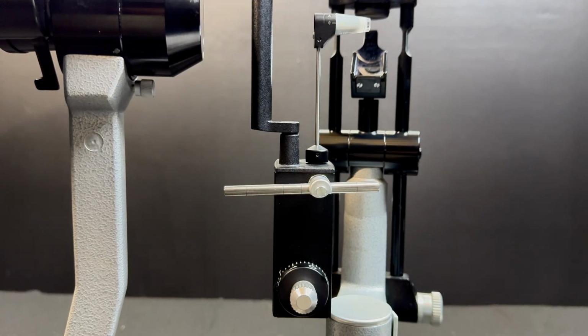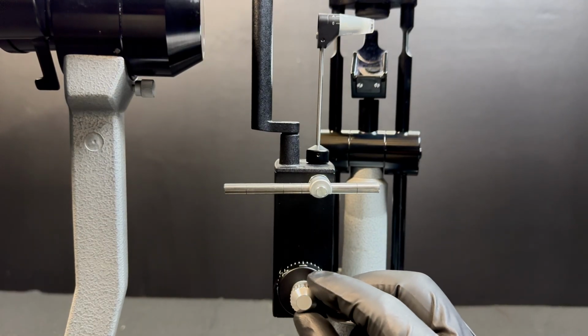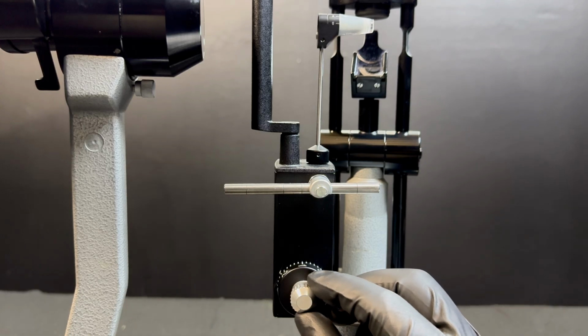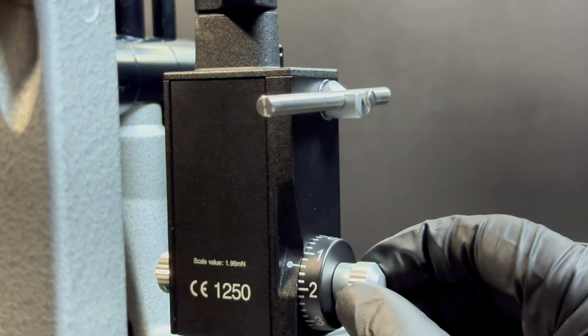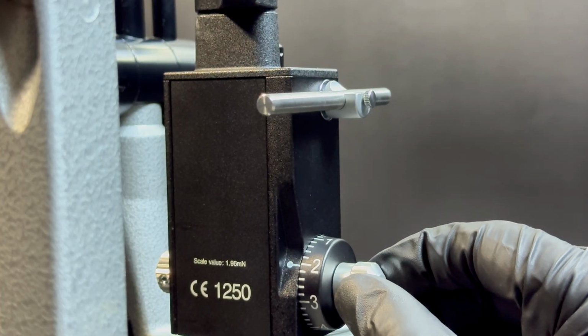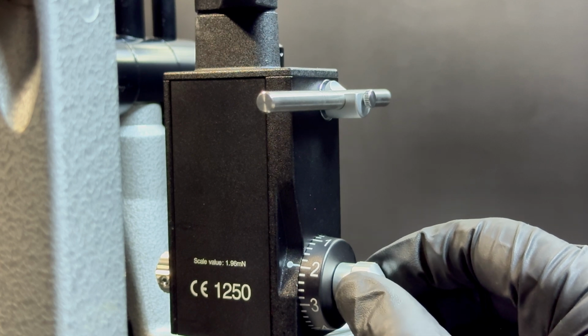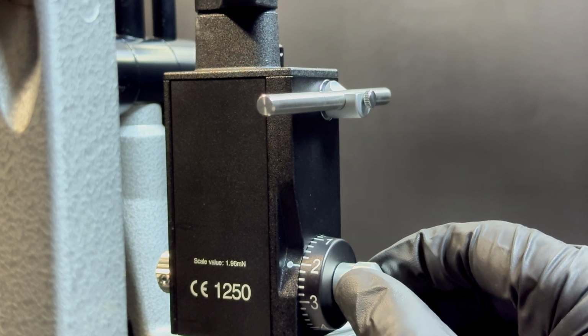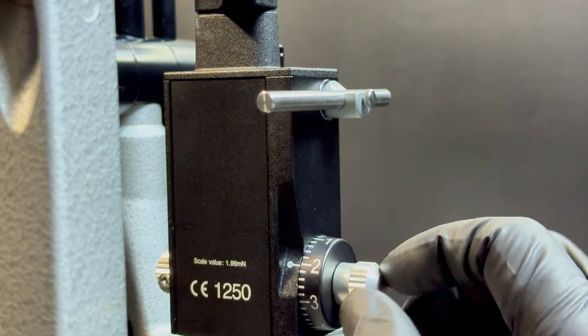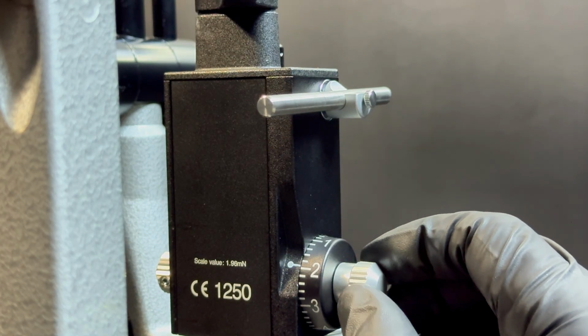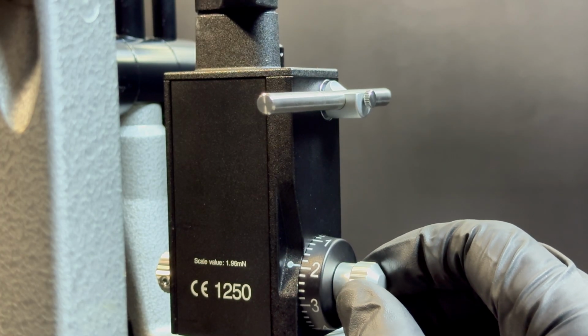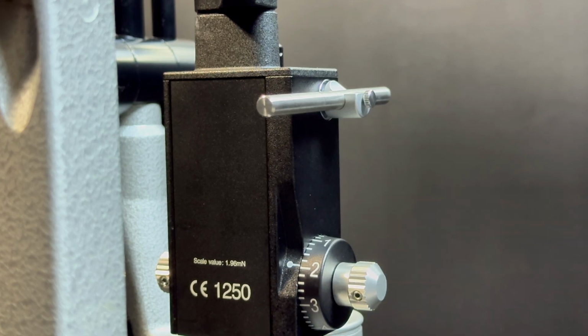Once connected, the calibration bar moves in sync with the feeler arm, so either one can be observed when checking calibration. At 2.05, the feeler arm should move toward the stop in the direction of the patient. At 1.95, the feeler arm should move toward the stop in the direction of the examiner. This alignment and feeler arm movement confirm the tonometer is in calibration.